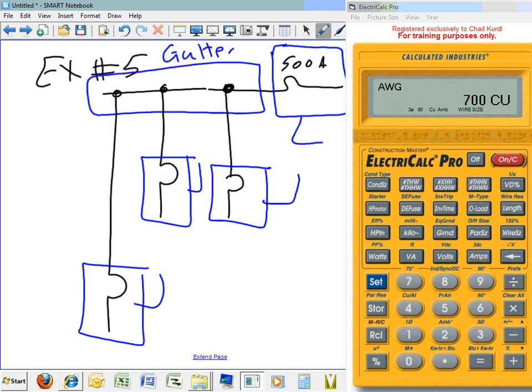From a reliability point of view, if you have any short circuit, ground fault, or malfunction from this point up anywhere in the system, you lose the whole system. So who cares if your system needs reliability? Data centers, hospitals, sport arenas. You can't lose heating and cooling in the building when you have thousands of people there. You better have what they do.